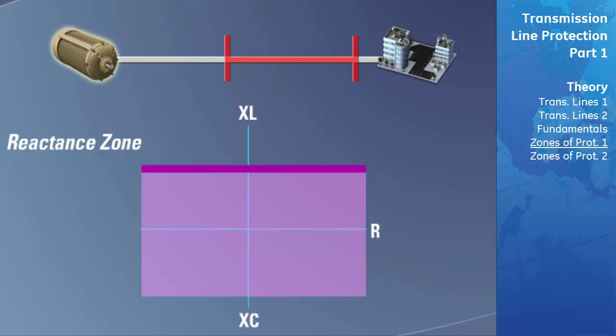For example, if an impedance zone detected the impedance of the line entering its zone of protection due to an external fault, the reactance zone can be used to block the impedance zone from tripping because it can determine that the impedance is mostly resistive and therefore the fault is not on the transmission line.